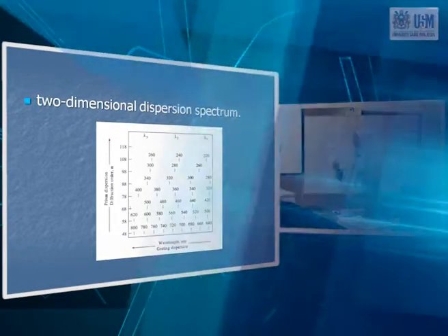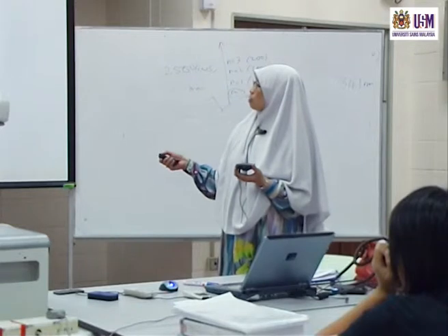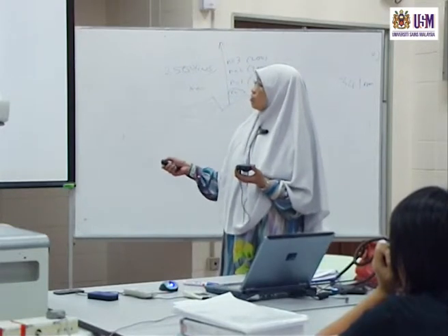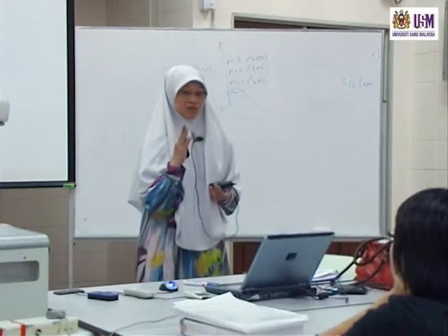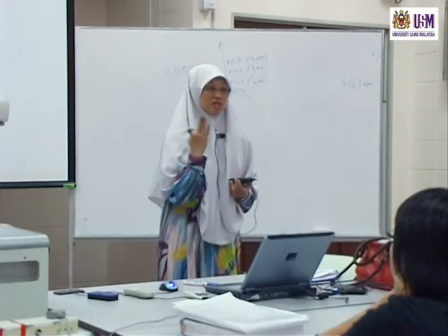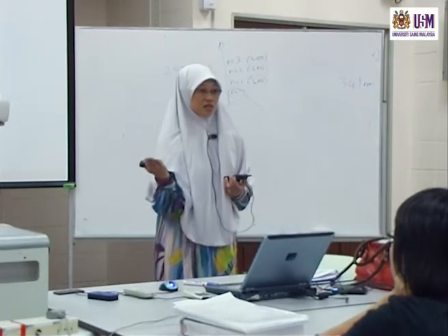Nothing different. So what you have here is a greater dispersion. So in case in your sample you have two wavelengths which are very close to one another, we can now choose the different wavelengths but using different orders so that they are further apart. Okay. So two kinds of monochromators, Echelle, the monochromators using the grating.